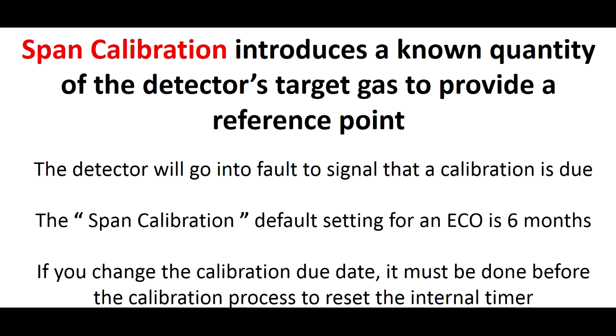The detector will go into fault to signal that a calibration is due. The factory calibration due date can be set between 1 and 12 months, with a factory default setting of 6 months. Facility-specific environmental conditions can affect the calibration period time frame. If you want to change the calibration due date, the change needs to be done before the calibration process to reset the internal timer.